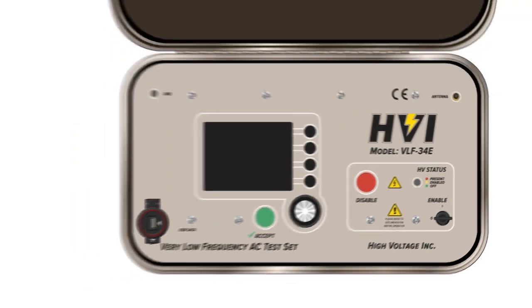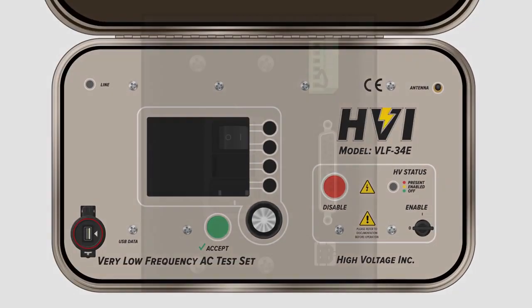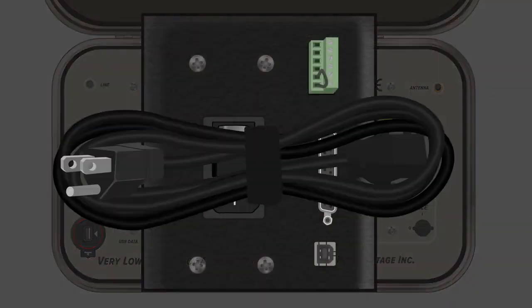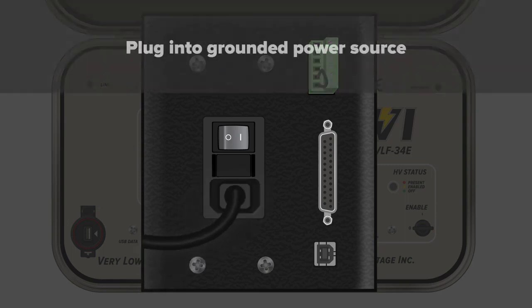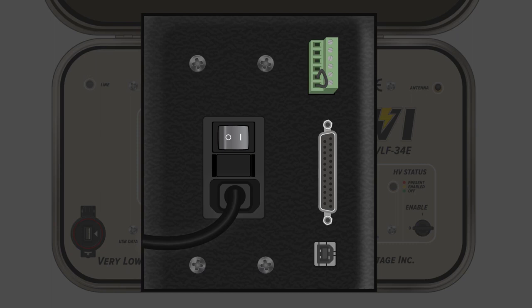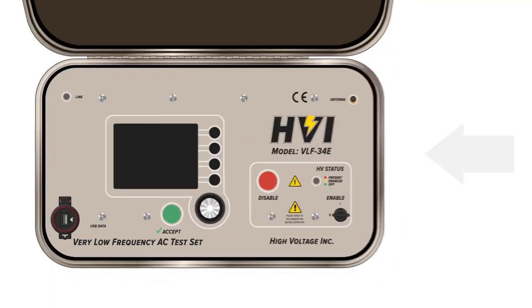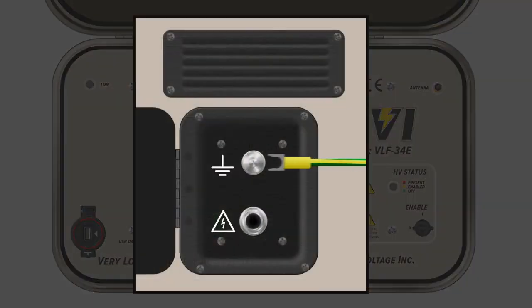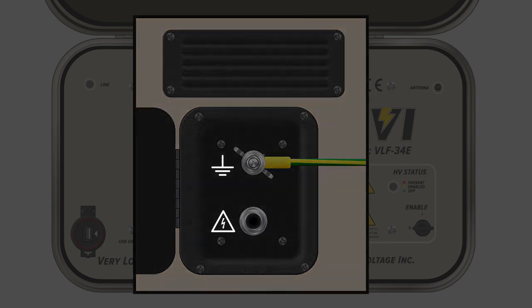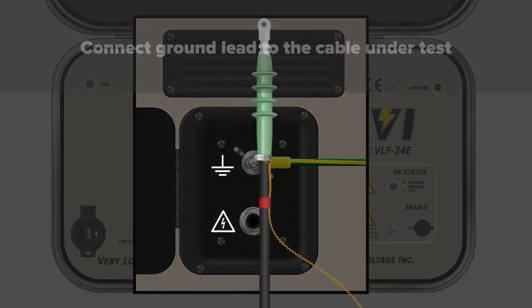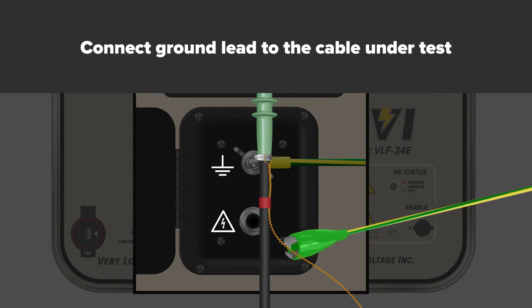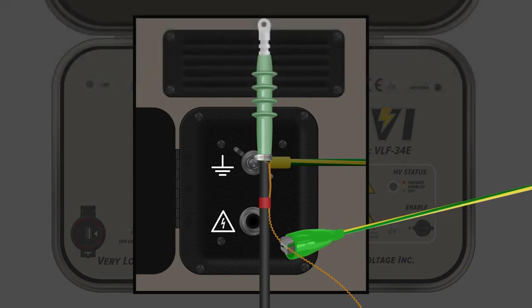Open the left side compartment and connect the main 3-prong power cable to the main power connection. Plug the main power cable into a grounded power source. Open the right-hand side compartment and connect the green-yellow ground lead to the ground stud using the forked prong end. Once the ground return lead has been connected to the high pot, extend the lead toward the cable being tested and use the alligator clamp to connect to the shield of the cable.